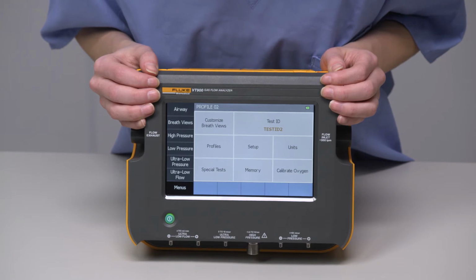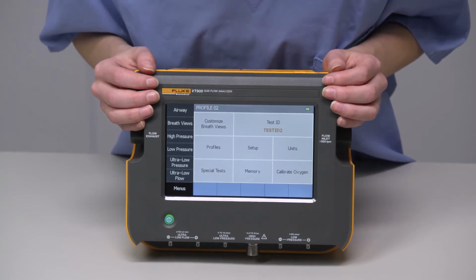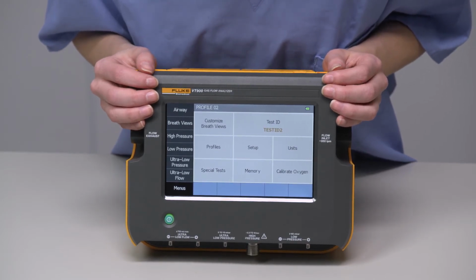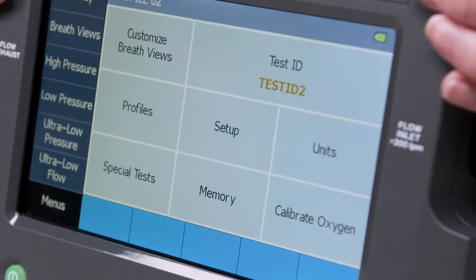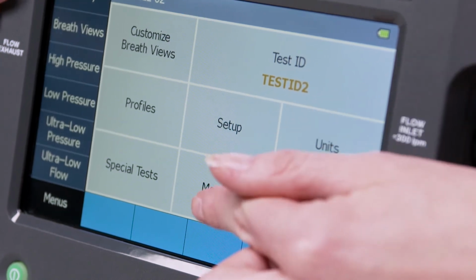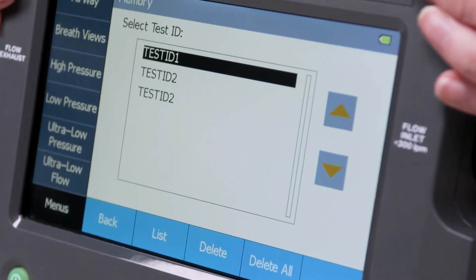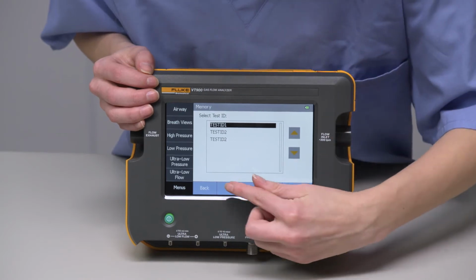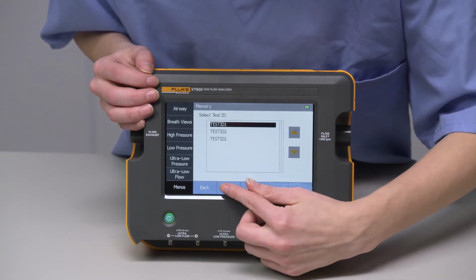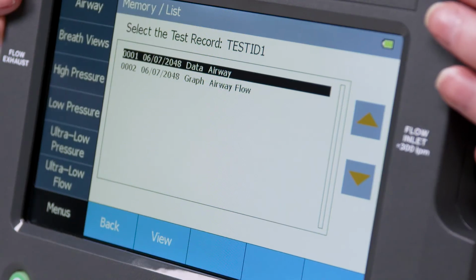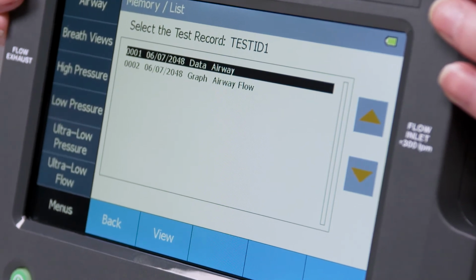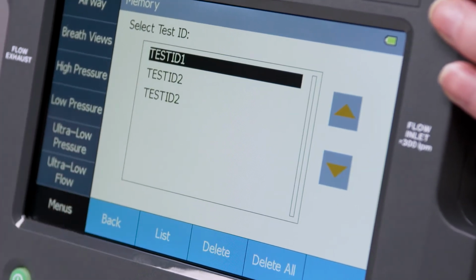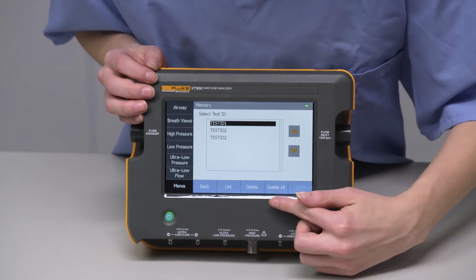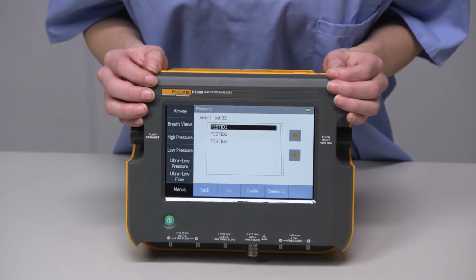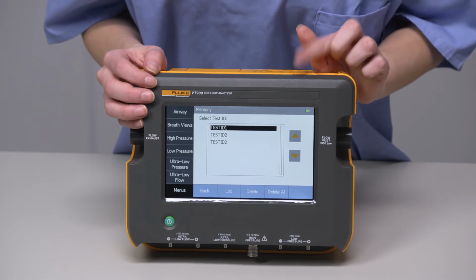You'll have to replace the oxygen sensor depending on how much you use it, but it's usually about 2 years for a VT900 and 1 year for the VT650. Back in the main menu, Memory will show us all of our saved test information. We can see lists of the test IDs. Test IDs are equivalent to the specific device you're testing. We can view the test data in the test ID, delete one or all, or send the test report to your computer using the micro USB.